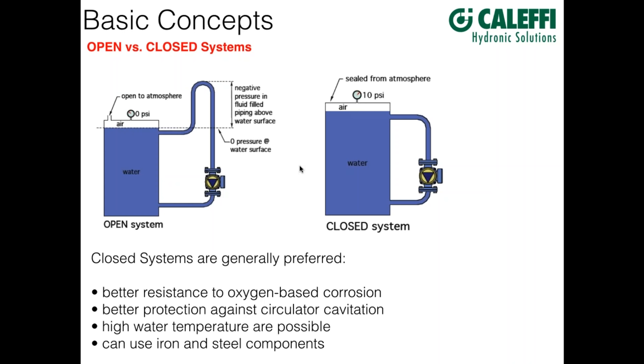There are two types of hydronic systems: open and closed. An open system has at least one point open to the atmosphere, which prevents the system from building up pressure. There are successful applications for open systems, but they have issues to respect. Any piping that goes above the water line in the tank is going to be under negative pressure, especially when the circulator is off. That's not necessarily a problem unless you have an air vent up there or if the pressure drops low enough that the water could actually flash from liquid into vapor.